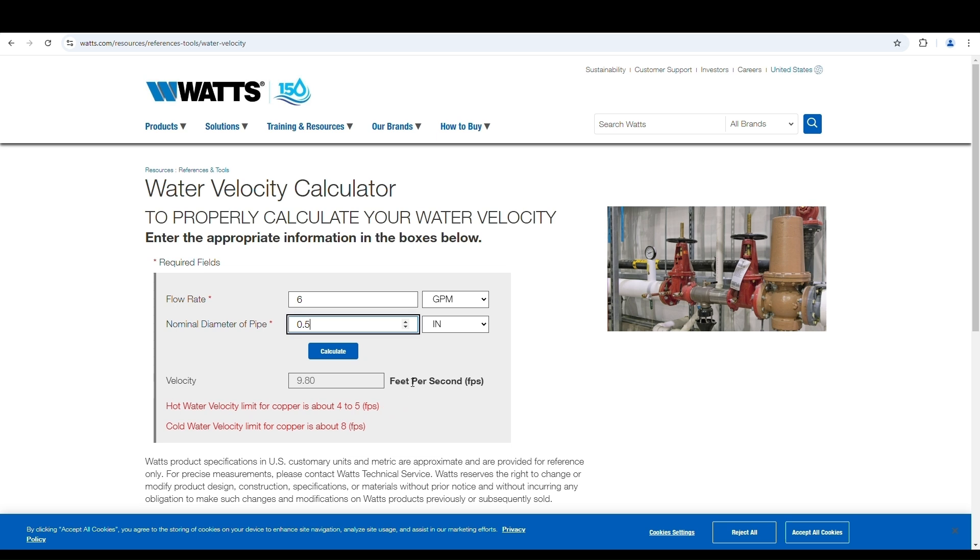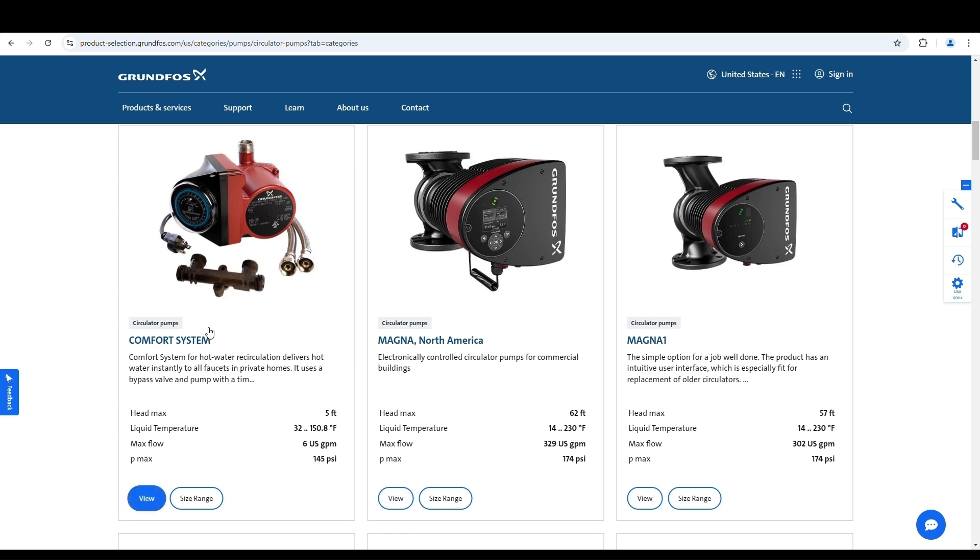Hot water velocity limit for copper is 4 to 5 FPS, feet per second. Look at this: 9.8. That's almost double the recommended maximum. Why is it recommended? Because the higher you go in the speed in feet per second, the more it's likely to wear away the inside of your copper pipe. So you've got to be careful with this if you just go out and buy any old pump.